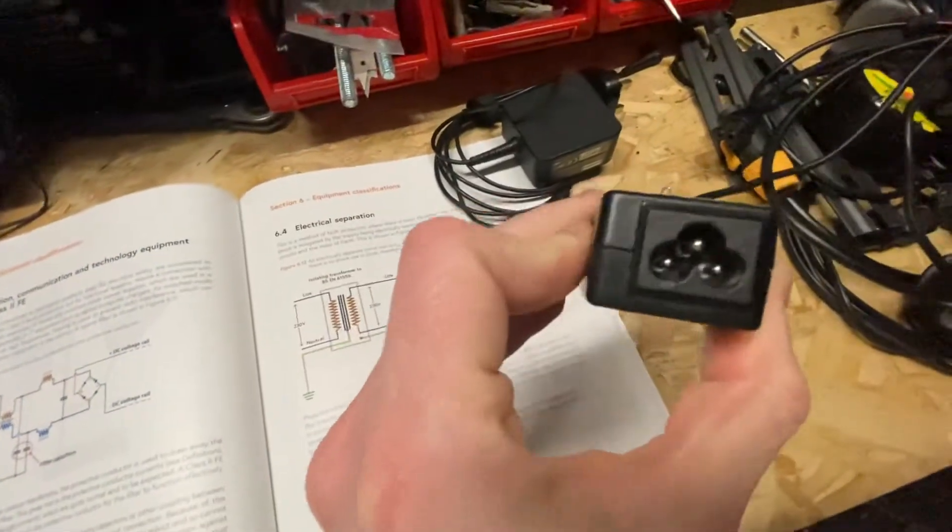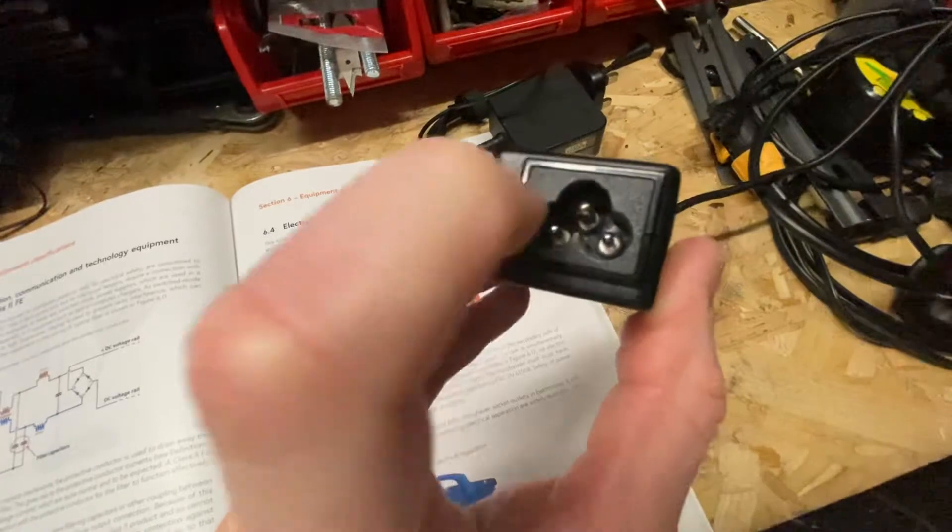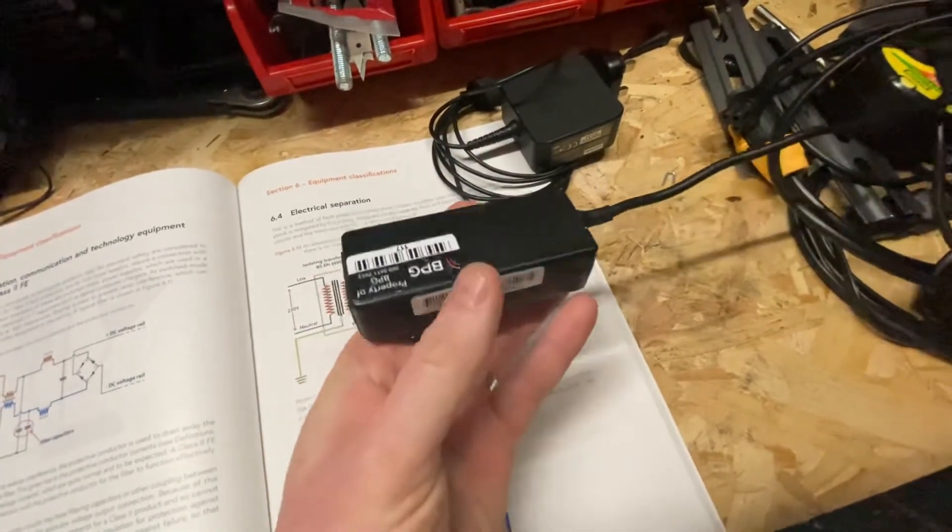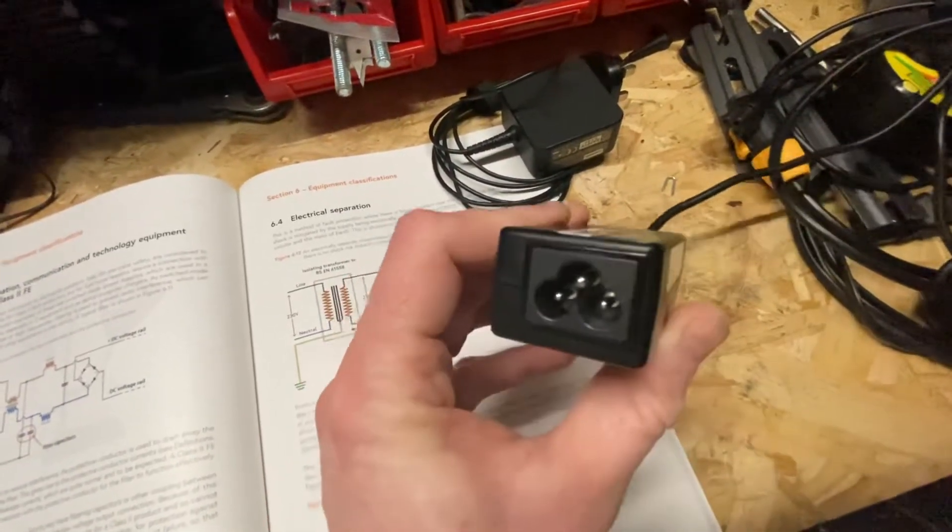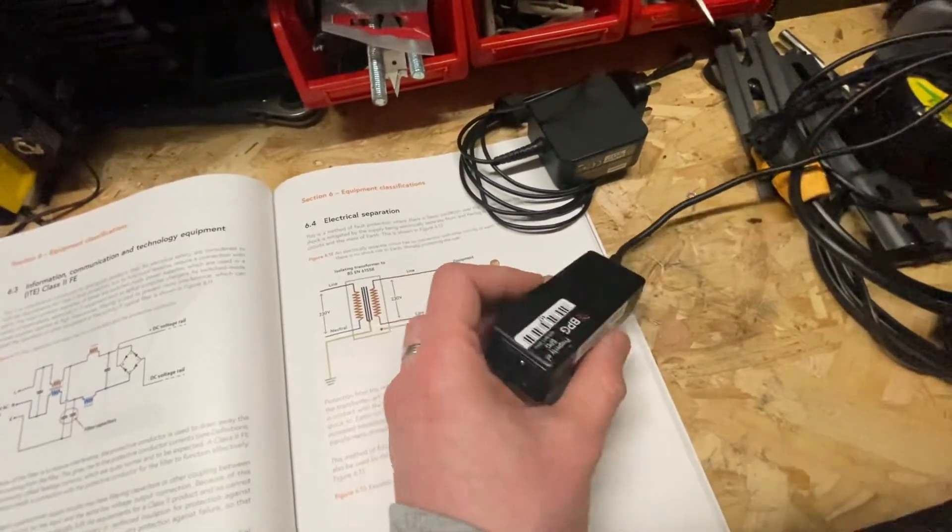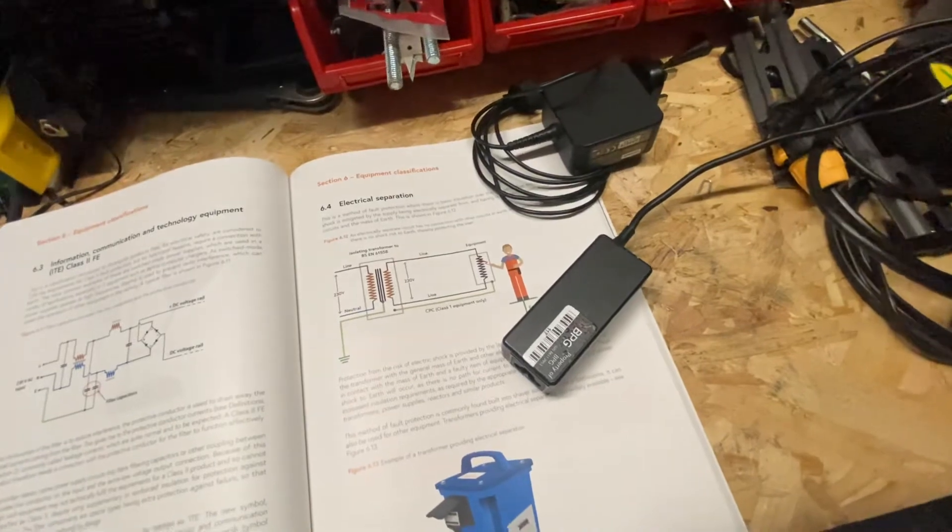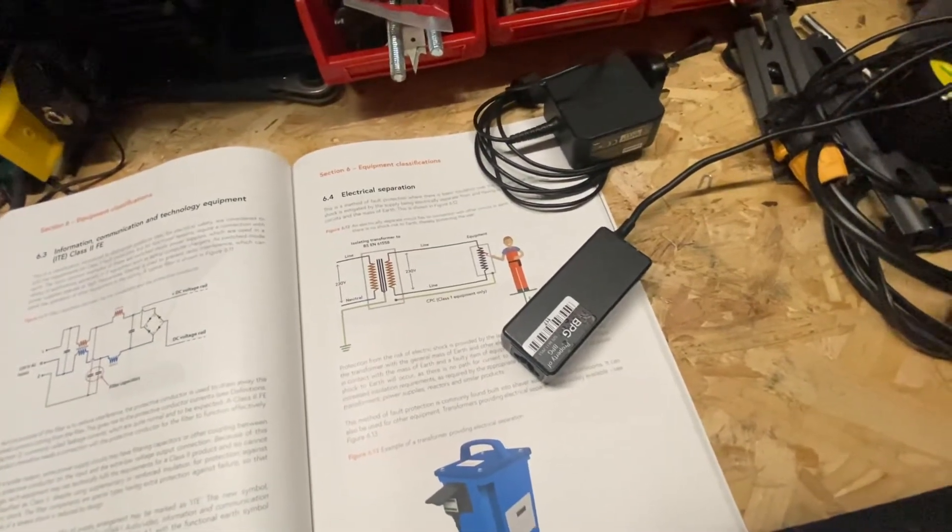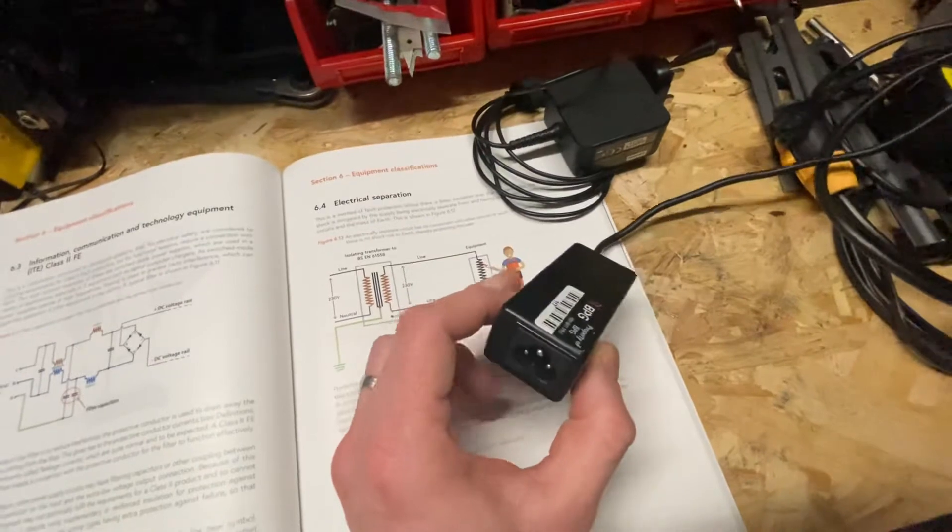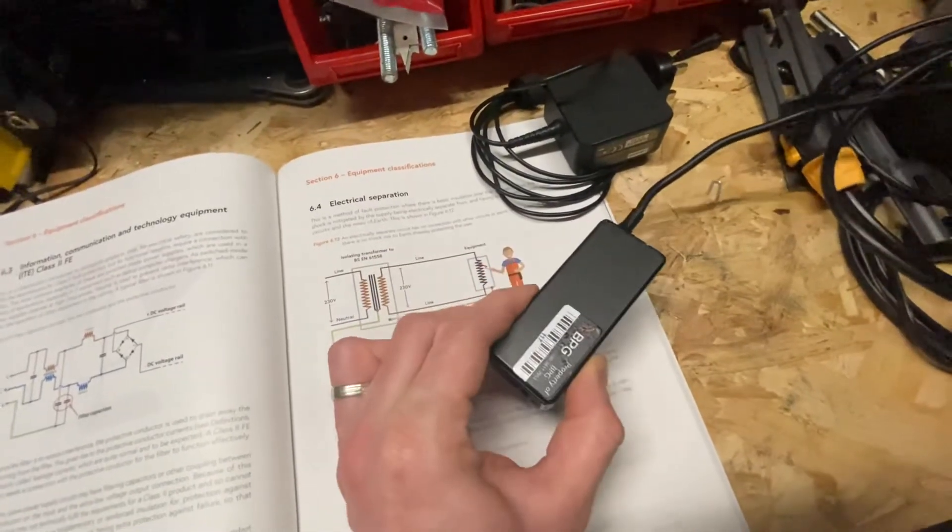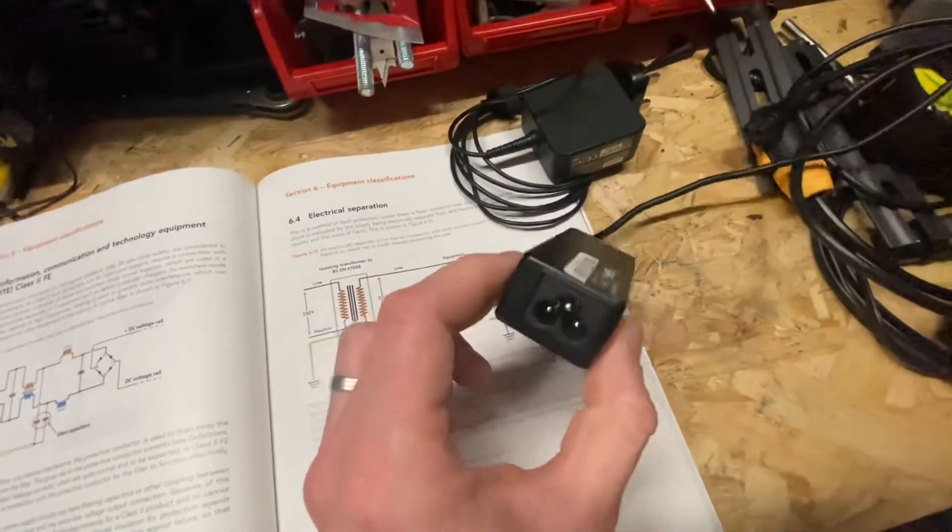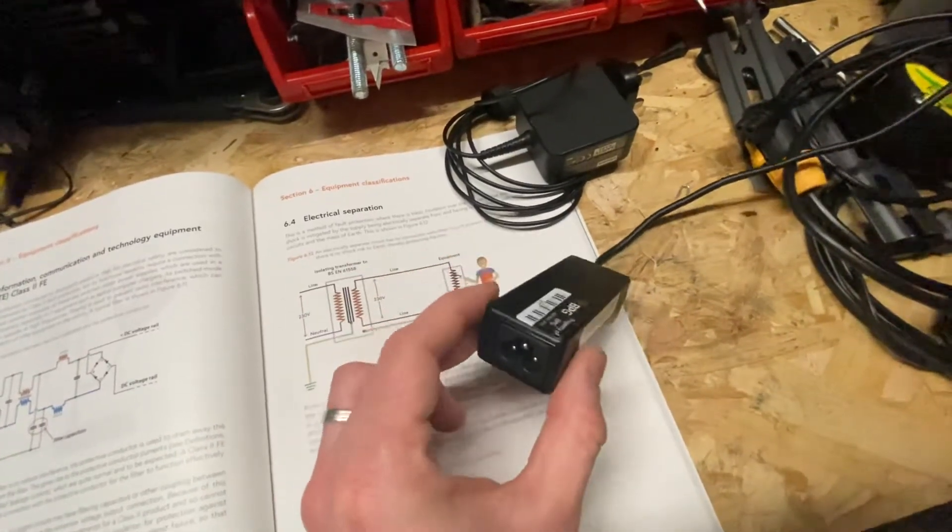But then on these, you see that they've got a functional earth in there. And that basically means that the parts inside need an earth to reduce interference and drain away small currents from the filters inside. So it needs that earth to be able to function properly. But it's not classed as a class 1 appliance.